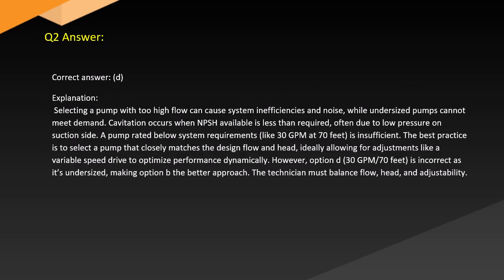Answer. Correct answer: D. Explanation. Selecting a pump with too high flow can cause system inefficiencies and noise, while undersized pumps cannot meet demand. Cavitation occurs where NPSH available is less than required, often due to low pressure on the suction side. A pump rated below system requirements, like 30 GPM at 70 feet, is insufficient.